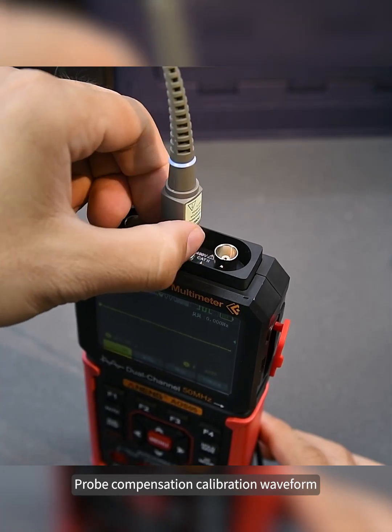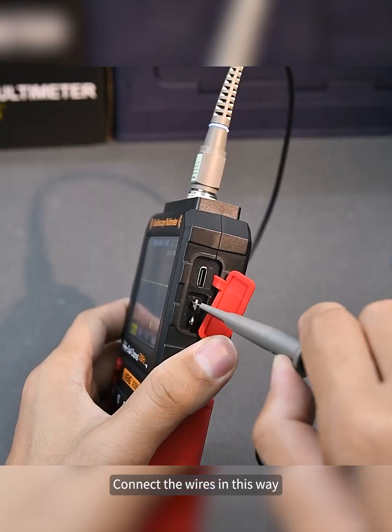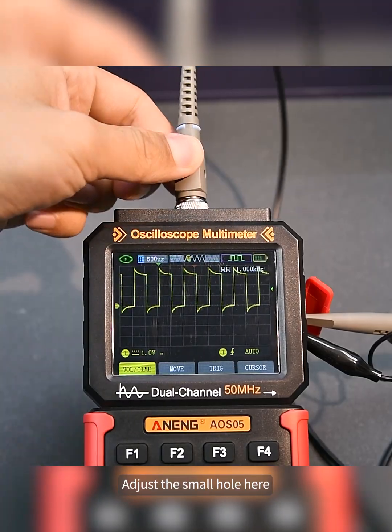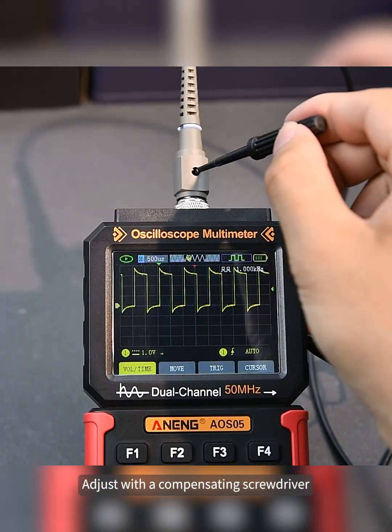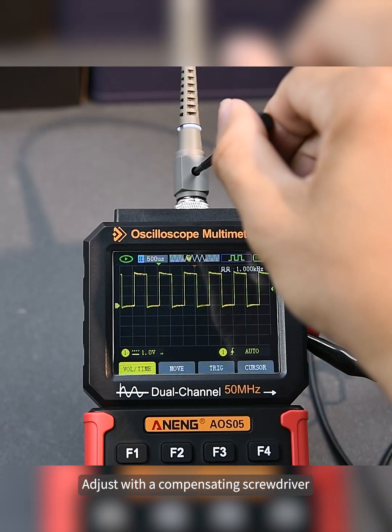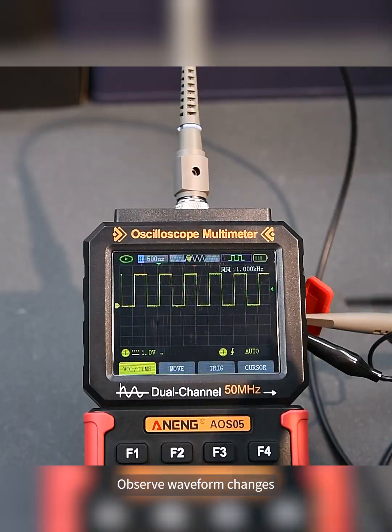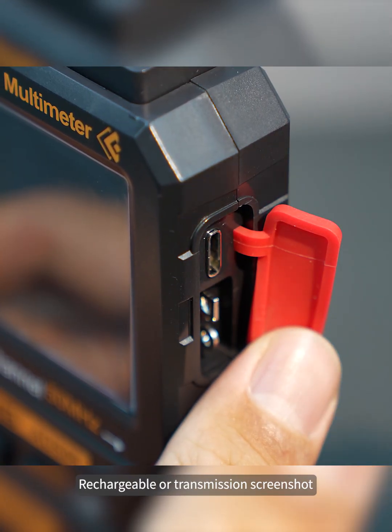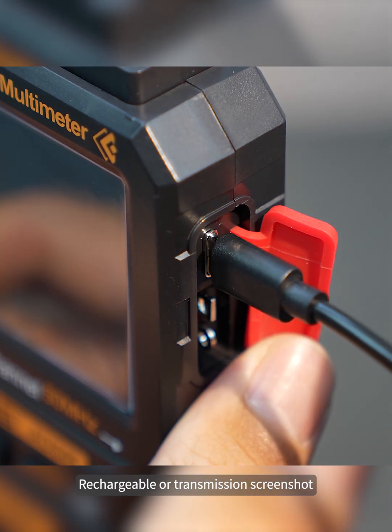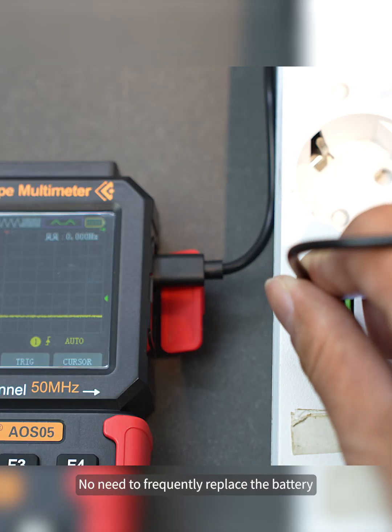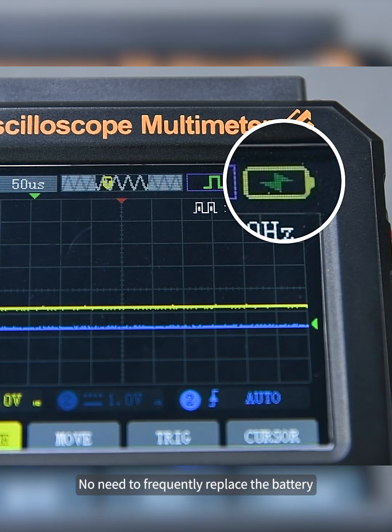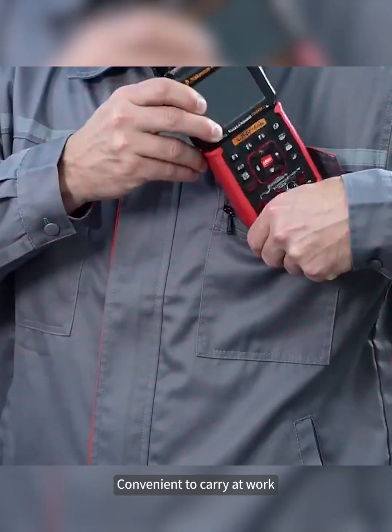Probe compensation calibration waveform. Connect the wires in this way. Adjust the small hole here with a compensating screwdriver. Observe waveform changes. Use the Type-C port for recharging or transmitting screenshots. Built-in battery, no need to frequently replace the battery. Convenient to carry at work.